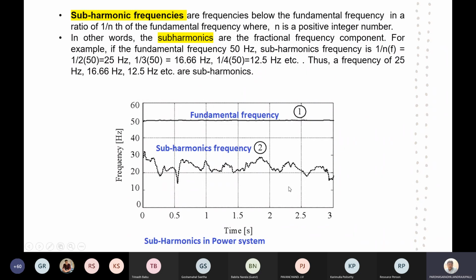From these two slides, I just want to convey one more time that the fundamental frequency is 50 Hz. Above that, if it is not part of the multiples of the fundamental frequency and it is more than the fundamental frequency, it is said to be an interharmonic. Whereas subharmonics are below the fundamental frequency, at 1 by nth of the fundamental frequency.